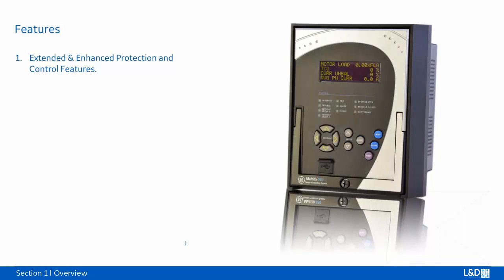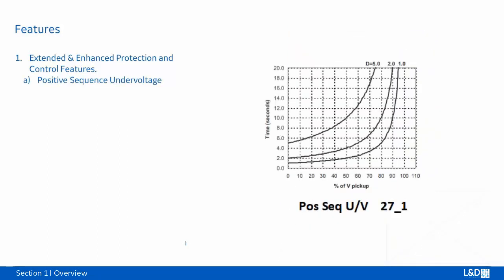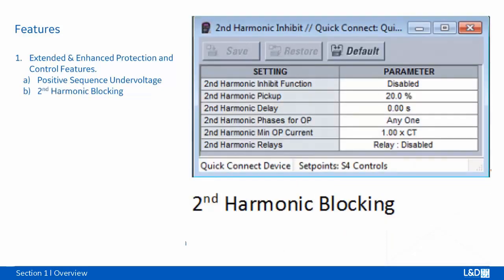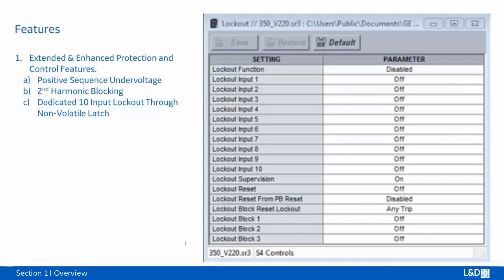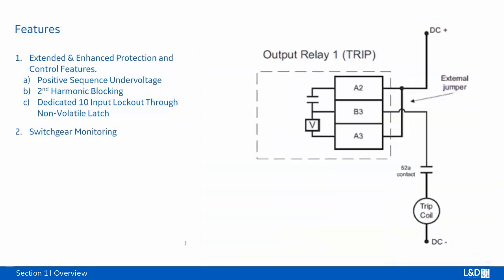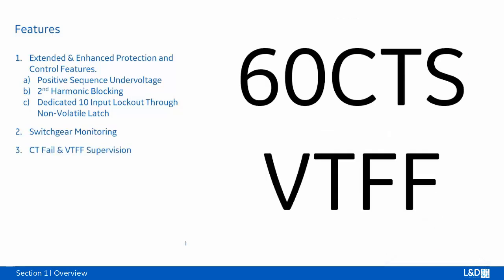Extended and enhanced protection and control features. Positive sequence undervoltage. Second harmonic blocking to avoid unwanted trips during normal operations. Dedicated 10 inputs lockout through non-volatile latch to simplify logic for lockout operation. 3 Series can monitor the integrity of both the breaker trip and closing coils and circuits. It also monitors the breaker operation parameters like tripping, closing, and spring charging time, number of permissible operations, magnitude of breaking current, mechanical wear, and contact wear. CT failure supervision and VT fuse failure supervision are provided to avoid undesired operation of some protection elements.